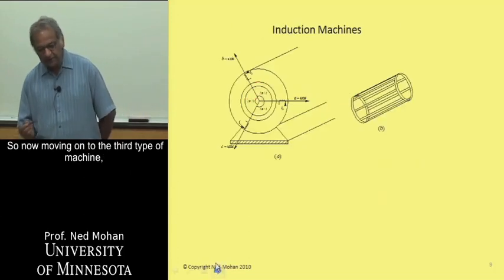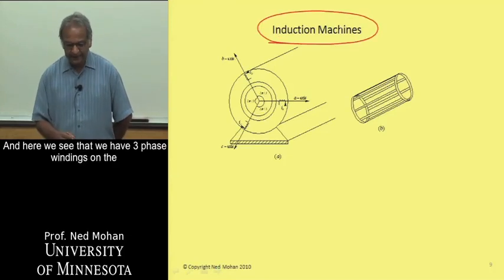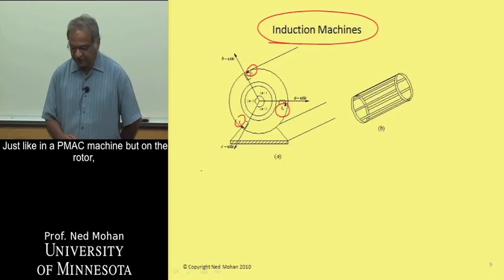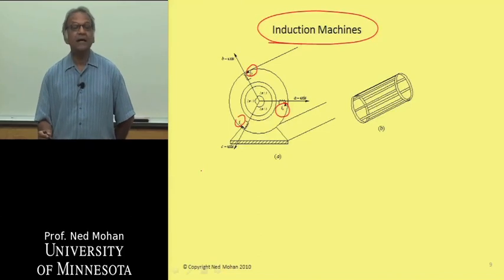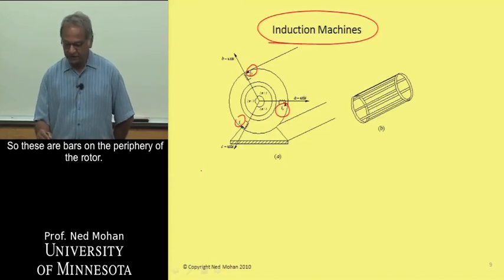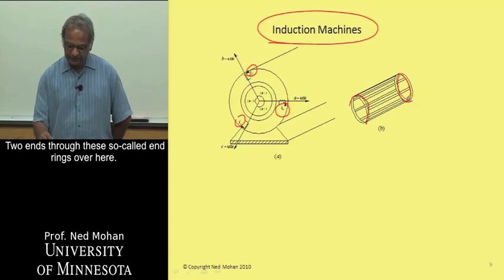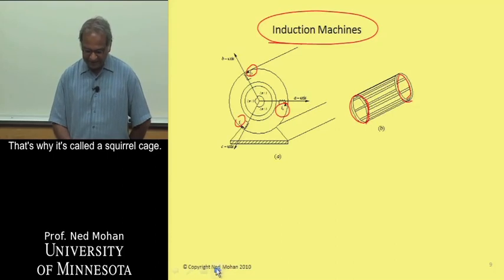So now moving on to the third type of machine, which is an induction machine, really a workhorse. And here we see that we have three-phase windings on the stator, A, B, and C, just like in a PMAC machine. But on the rotor, instead of magnets, we have a squirrel cage. So these are bars towards the periphery of the rotor, copper bars, which are then short-circuited at two ends through these so-called end rings over here. And that's why it's called a squirrel cage.